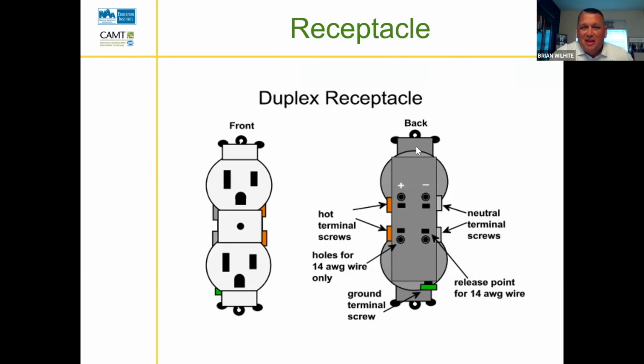All right. So if we look, we can hook our wires to the neutral side and hot side via the screws, or they give us an option here to plug the wire into the back of the receptacle, with the bottom square being our release. So if we press the wire into the back of the receptacle, in order to release it we'd have to take a small thermostat screwdriver into the square there, and that would release the wire. I have issues with the plug-in type on the back of these, and maybe Candace can tell us her opinion on them, but on some new construction, I've had it where those wires have popped out and have not made a good solid connection.